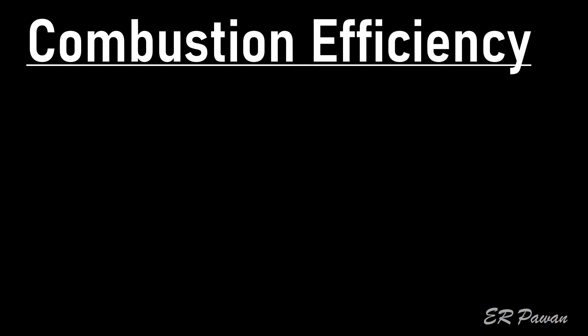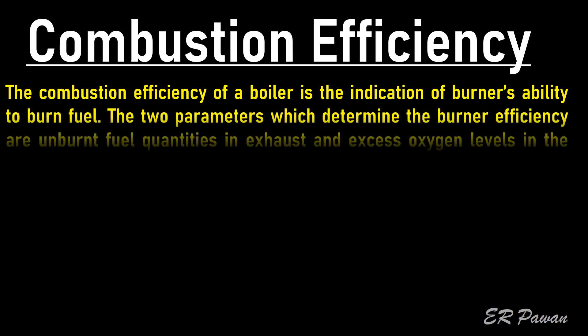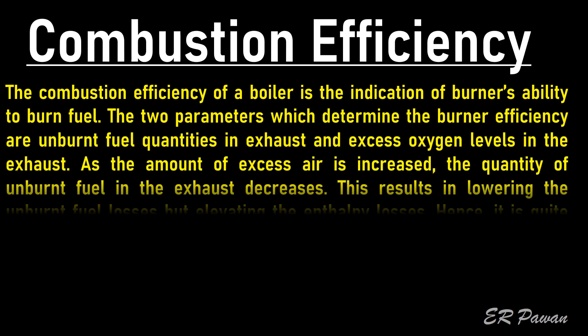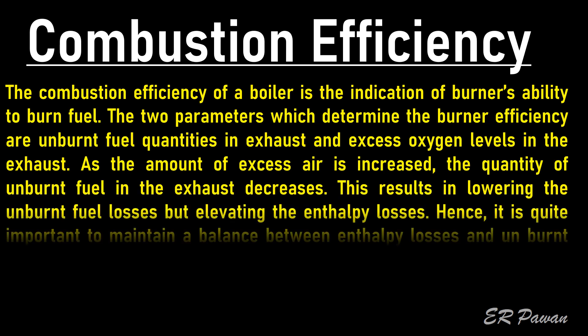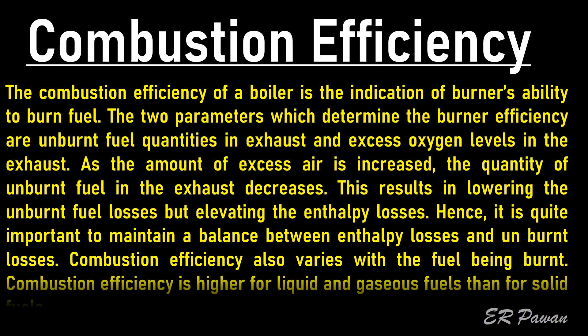Combustion efficiency: The combustion efficiency of a boiler is the indication of the burner's ability to burn fuel. The two parameters which determine the burner efficiency are unburned fuel quantities in exhaust and excess oxygen levels in the exhaust. As the amount of excess air is increased, the quantity of unburned fuel in the exhaust decreases. This results in lowering the unburned fuel losses but elevating the enthalpy losses. Hence, it is quite important to maintain a balance between enthalpy losses and unburned losses.